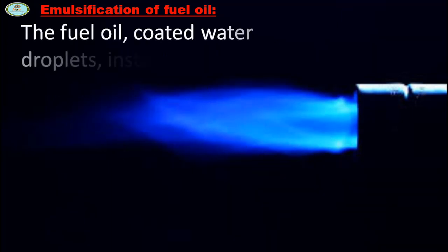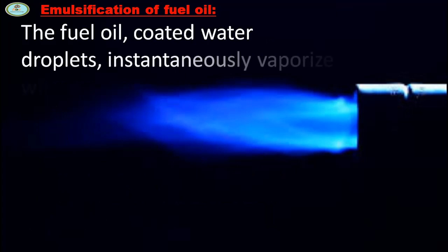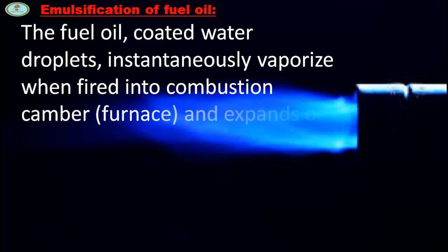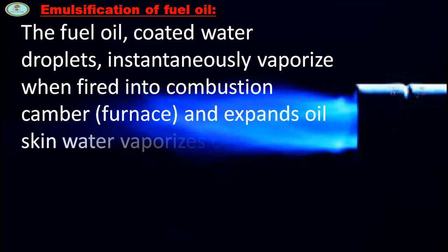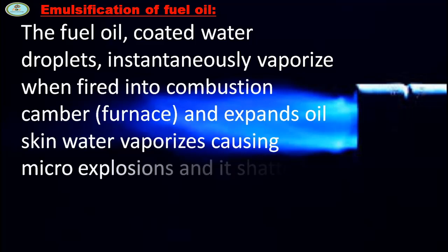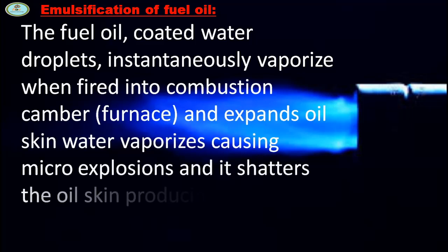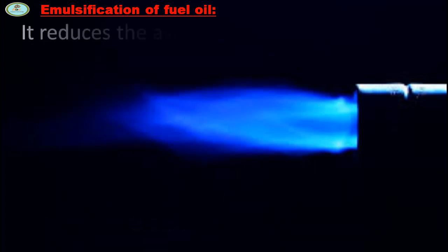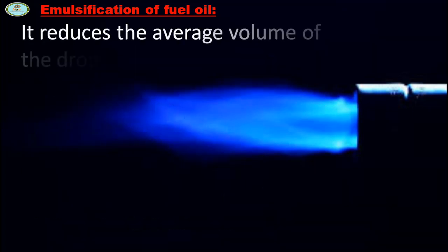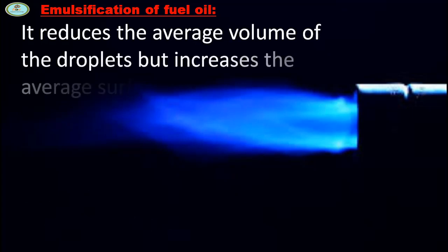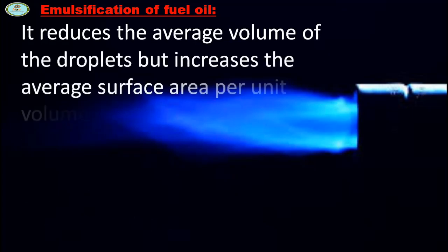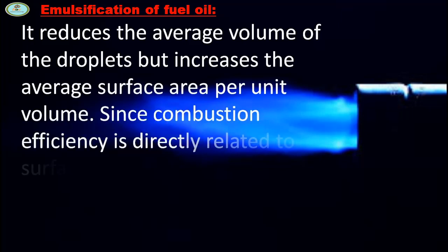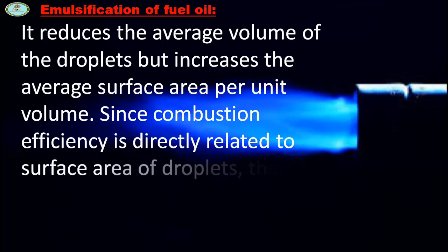The fuel oil coated water droplets instantaneously vaporize when fired into the combustion chamber and expand. The oil skin water vaporizes, causing micro explosions that shatter the oil skin, producing much finer secondary atomization. This reduces the average volume of the droplets but increases the average surface area per unit volume.